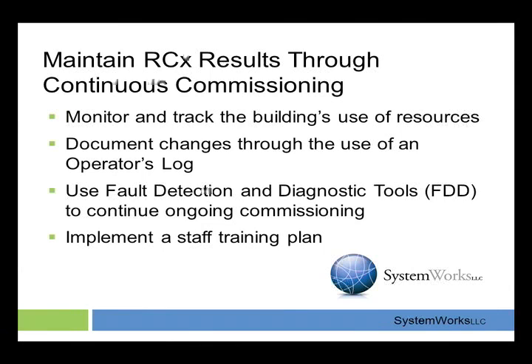Staff training plan is about making people aware, so that your building people don't, say, leave a fan that is scheduled to shut off at 3 o'clock running. Instead of going through the automation system when there's an event on Tuesday night, they put that fan in hand mode and then forget about it, and now we're back to 24/7 operation. That's training, so the staff operates the equipment the right way so that it's only on that one night.